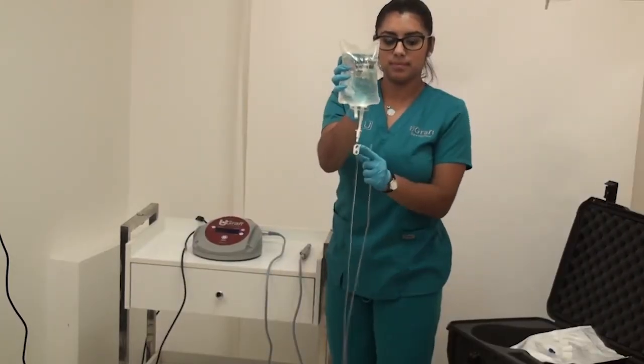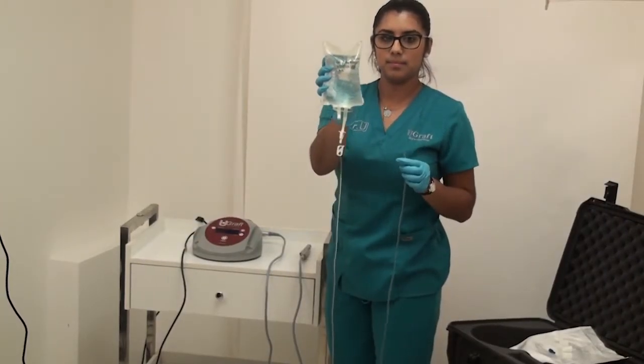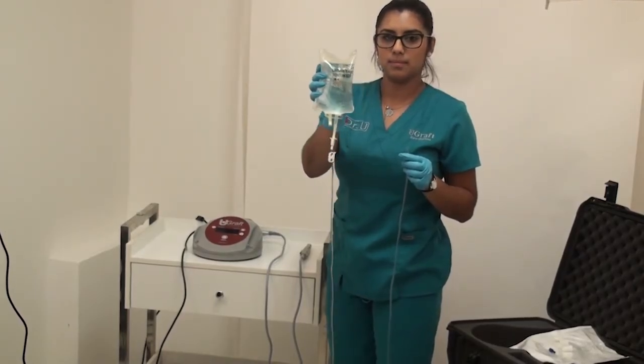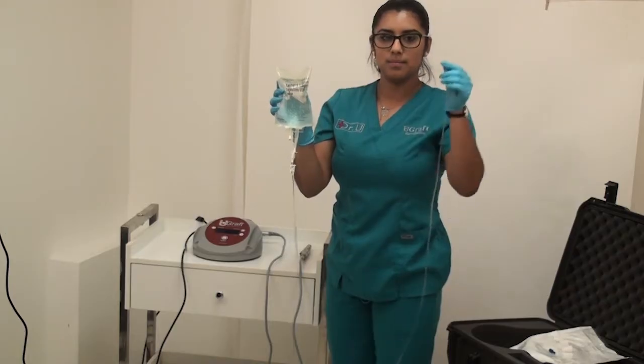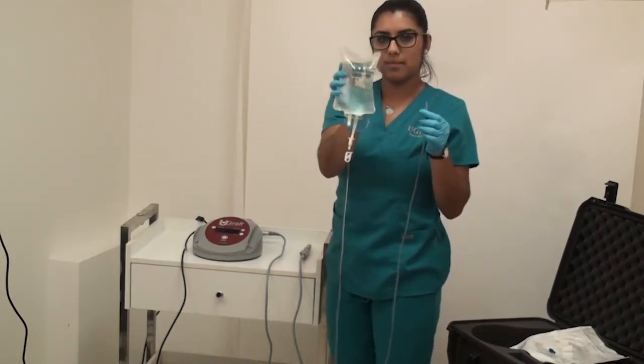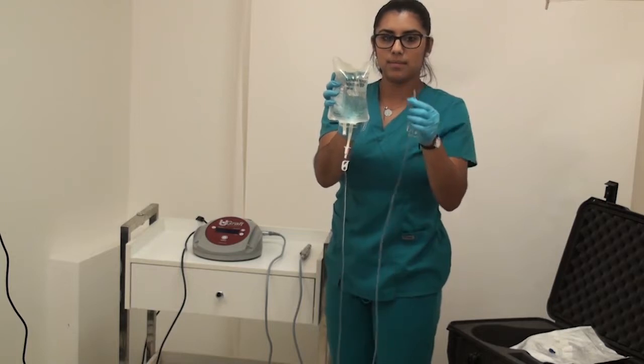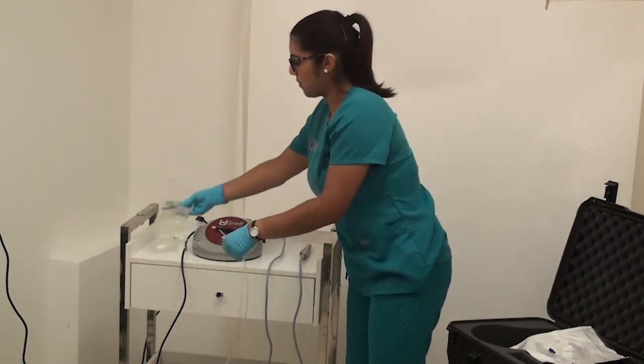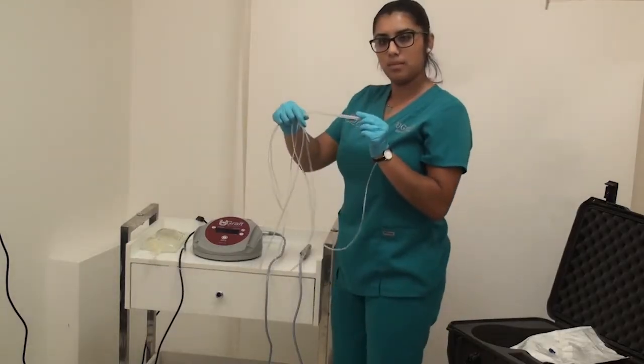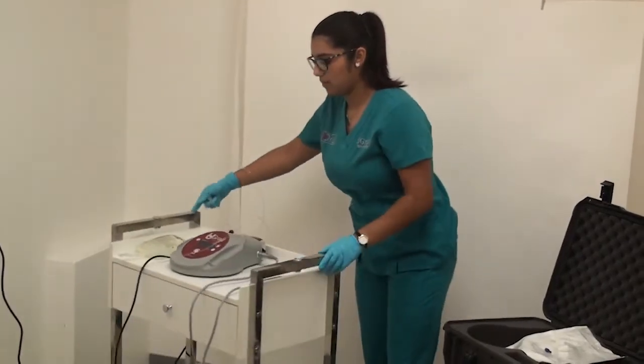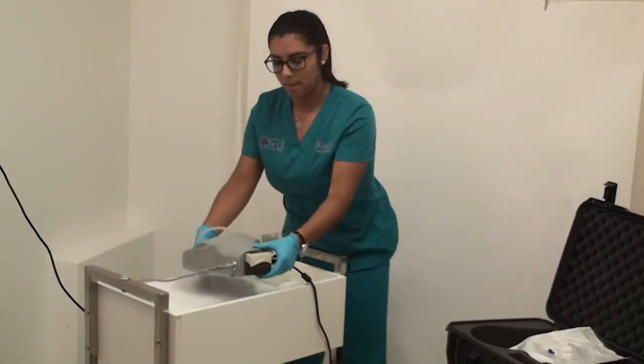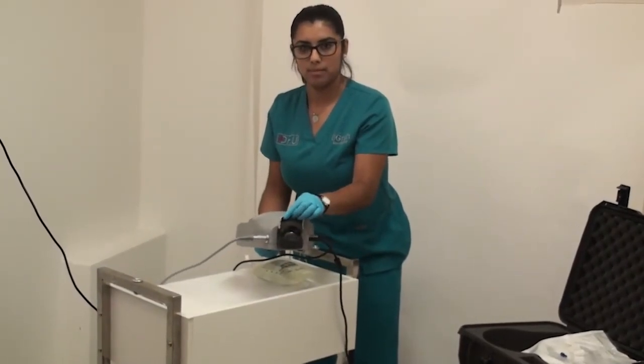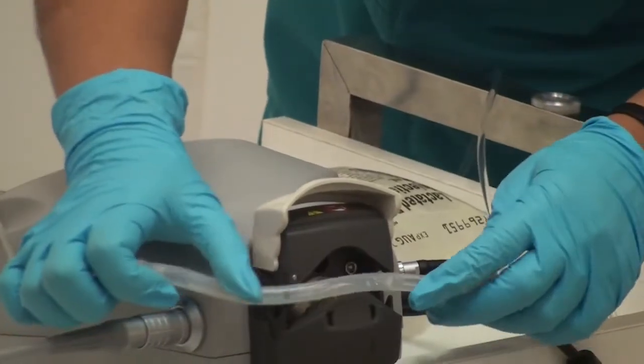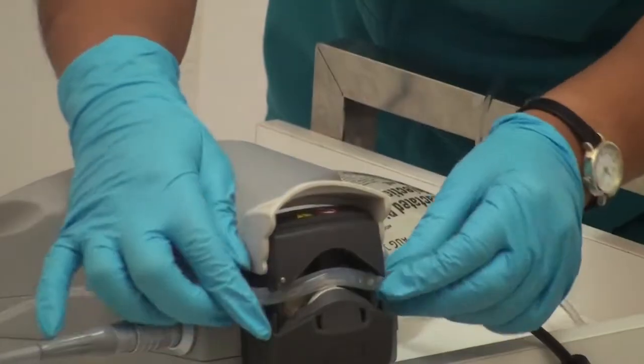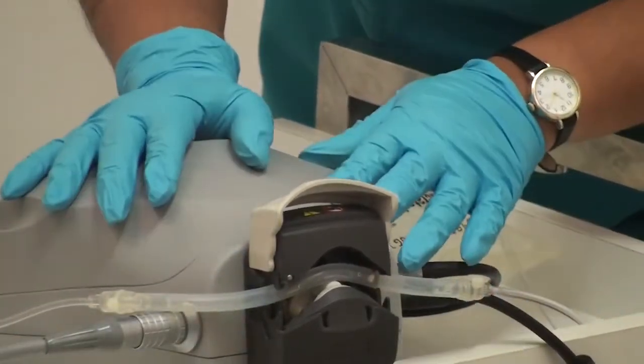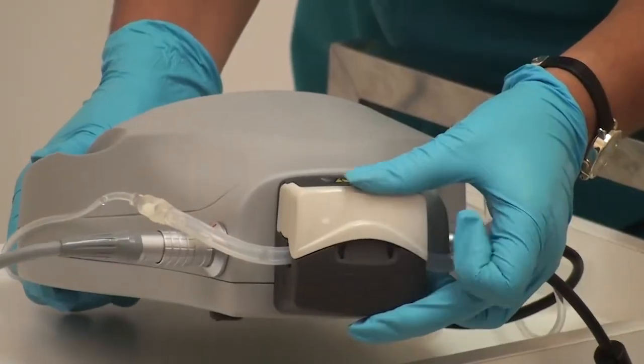Next is connecting the fluid system to the console. With the operator facing the console, the bag should be on his left-hand side, the console in the middle, and the handpiece on the right side. This is so that the fluid would flow from the bag to the handpiece and not from the handpiece to the bag. With the physiologic fluid on your left, thread the largest part of the tube through the fluid pump system located on the back of the console. You do so by unsnapping the pump hood to open it. Next, thread the larger part of the tube through the pump. Once it's in place, snap the pump hood closed to secure the tube in place.